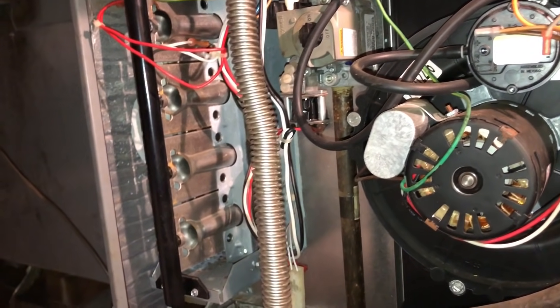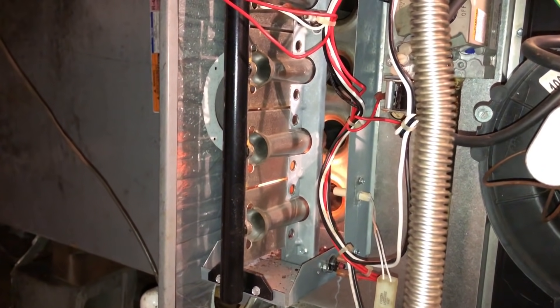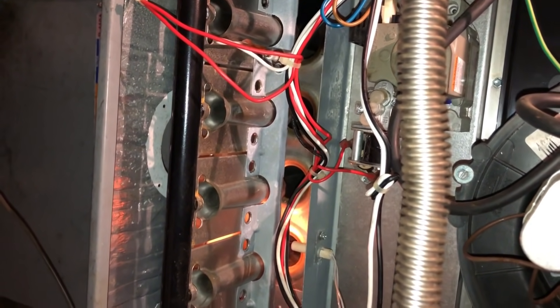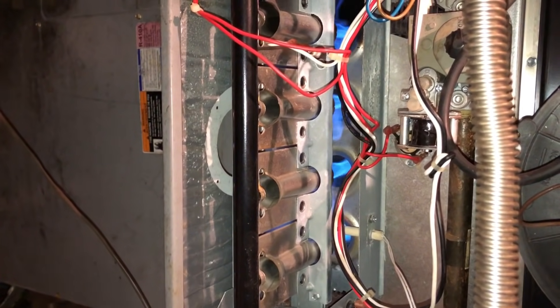Let's see if they do an ignition. And there was the rollout up top — it's still there. Let me cut this line off. See all that rollout? It's looking pretty bad.